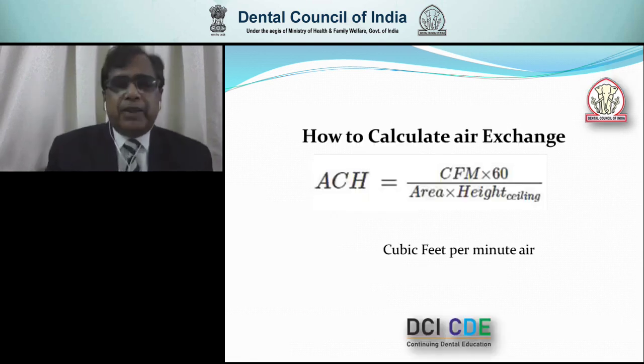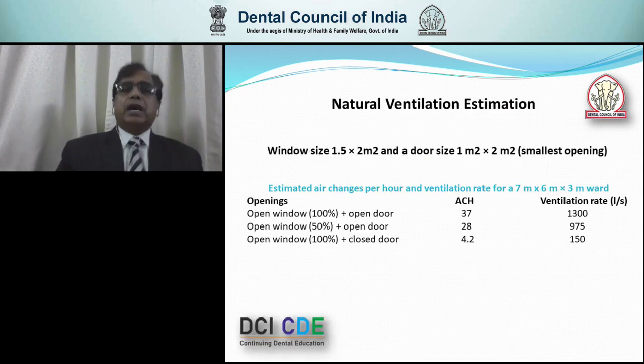A very simple way to calculate is to look at how many windows and doors are present in your clinic or home. If a window size is 1.5 by 2 meters square and door size is 1 by 2 meters square, even with the smallest opening, the estimated air changes per hour for a 7 by 6 by 3 meter ward, which is a very big ward, is 37 air changes per hour if the window is 100% open and doors are 100% open. If open 50%, then 28. If windows are closed and only one window is open and door is closed, then only 4.